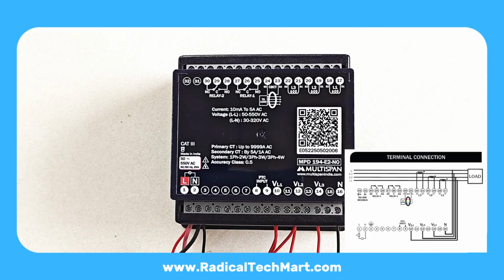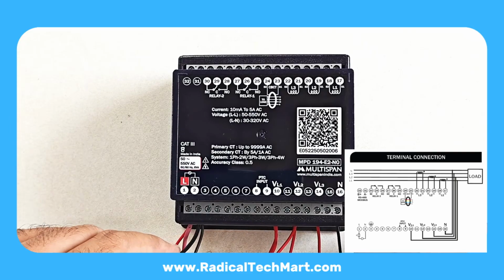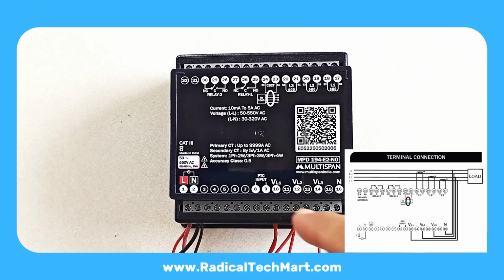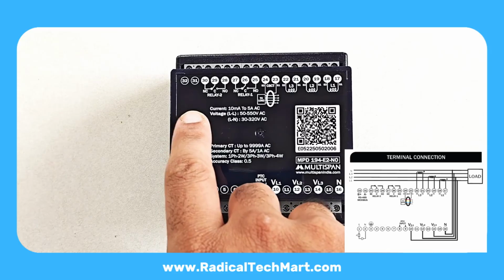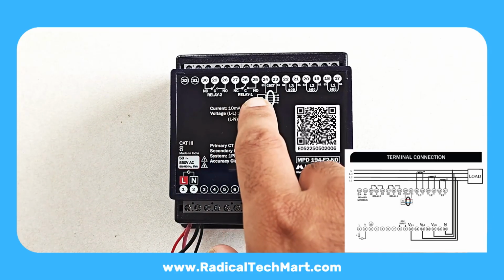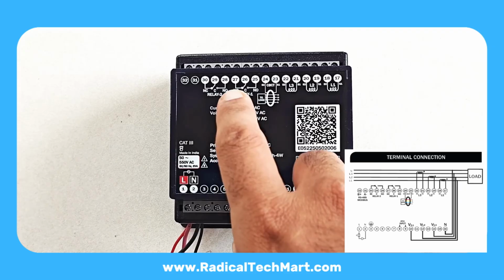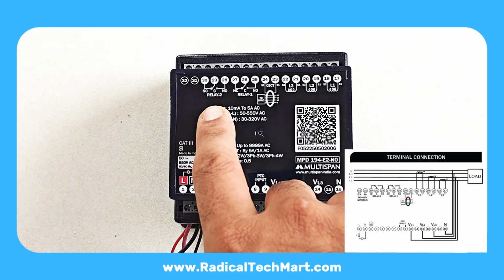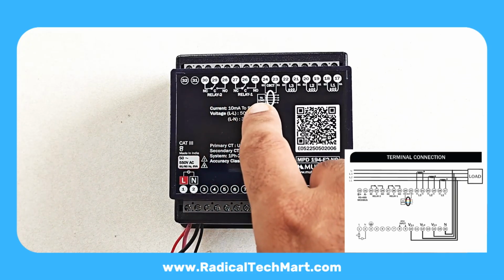Terminals 23 and 24, CBCT input. Here we connect the core balance CT. In a 3-phase 4-wire system, all 4 conductors, R, Y, B, and neutral, must pass through the CBCT. This allows us to measure earth leakage current and trip the motor if leakage exceeds the set value.